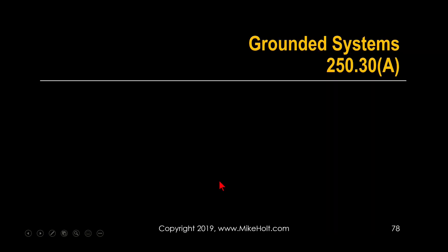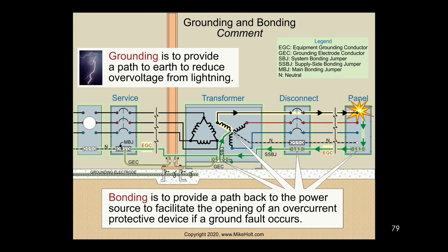Pretty much all transformers are separately derived systems. Let's take a transformer and follow the rules of 250.30. What are we trying to accomplish? Just like with services, we have to ground them and we have to bond them. So with separately derived systems, we take the secondary system and we're going to ground it.